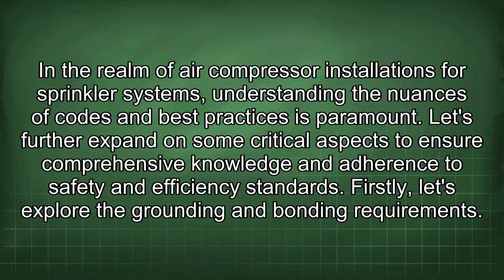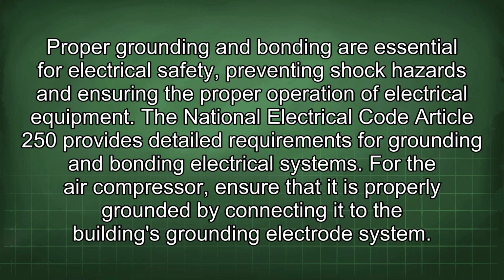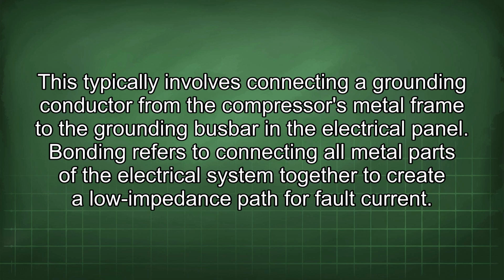Firstly, let's explore the grounding and bonding requirements. Proper grounding and bonding are essential for electrical safety, preventing shock hazards and ensuring the proper operation of electrical equipment. The National Electrical Code Article 250 provides detailed requirements for grounding and bonding electrical systems. For the air compressor, ensure that it is properly grounded by connecting it to the building's grounding electrode system. This typically involves connecting a grounding conductor from the compressor's metal frame to the grounding busbar in the electrical panel.